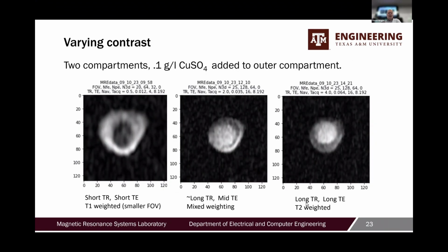We can change contrast. So here's two compartments. This has got distilled water in it. This has got distilled water with 0.1 gram per liter copper sulfate. This is a T1 weighted image, and you don't see the distilled water. And my parameters were bad, so it's low, relatively 15 kilohertz bandwidth. Decrease the resolution because I wanted better signal to noise. Change to a longer TR, mid TE. So this is mixed weighting, and now you see the distilled water and the copper sulfate, same intensity. Here we go to a very long TR, long TE, and now what you see is the distilled water and very little from the copper sulfate. So this is how clinical MRI is done. They want to measure T1 and T2, and you do that by controlling your pulse parameters.